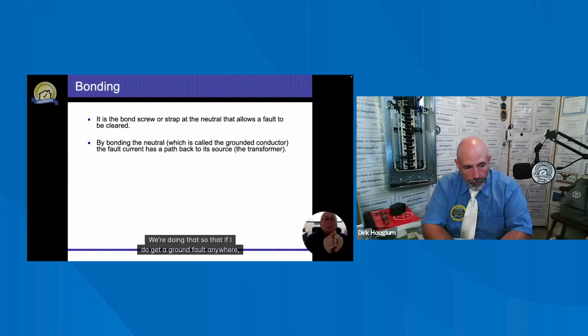We're doing that so that if I do get a ground fault anywhere, that's going to allow free flow of electricity, and we're going to basically change it into a short circuit, and that's going to be tripping the breakers. Without that bond, we're just going to be flowing electricity into the earth. We're not going to have enough flow to trip the breakers, so that bond is vitally important. When we open up our panels, the first thing that we're going to look for is the bond. I want to verify that I got my ground connection to my neutral connection.